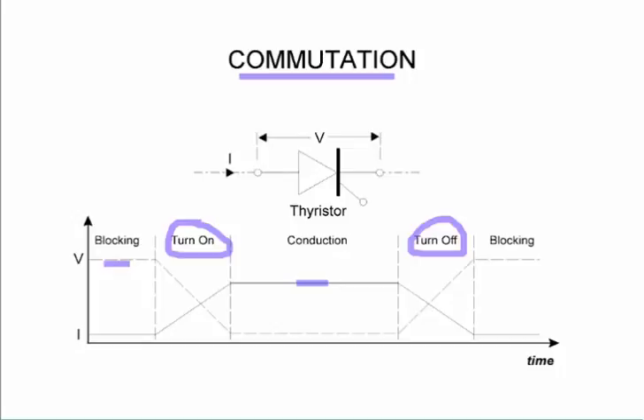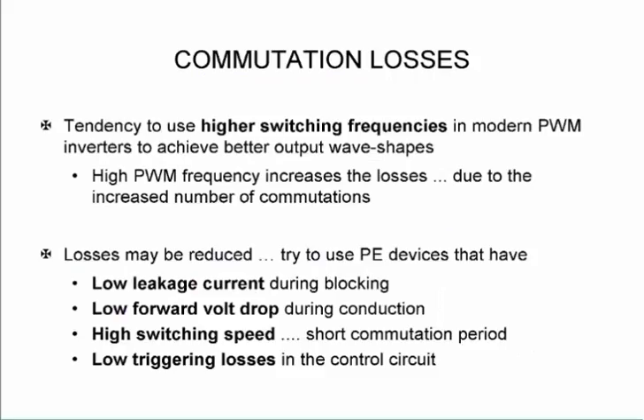During this turn on and turn off period we have a high power dissipation, which is also called the switching losses. So those switching losses will then increase if we increase the frequency, if we switch it on and off on a more regular basis. Now the tendency is to use higher switching frequency in our modern pulse width modulation inverters in order to achieve better wave shapes.